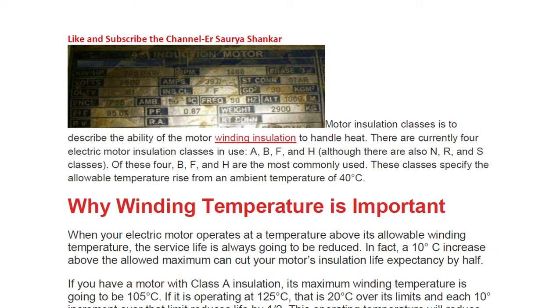What does F mean? By the end of this video you will be able to answer that. Motor insulation class describes the ability of motor winding insulation to handle heat. Heat is important because it destroys your motor. There are currently four electric motor insulation classes: A, B, F, and H, although there are also R and S classes. Of these, B, F, and H are the most commonly used.